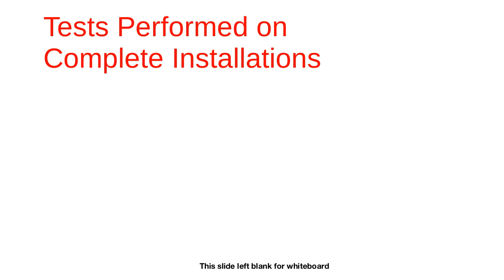This is to ensure, as we talked about in the September class, the importance and the necessity of the earthing system. You check if the earthing system has been correctly earthed. This is to ensure the safety of the whole installation and the safety of others. In electrical engineering, when you have a fault, sometimes you have seen faults being transferred through the KPLC wires from one building to the other. So the presence of means of earthing is an important factor to consider at the visual inspection stage.